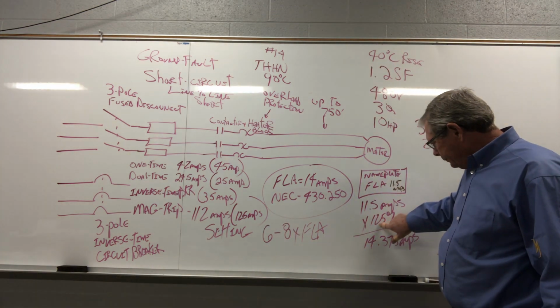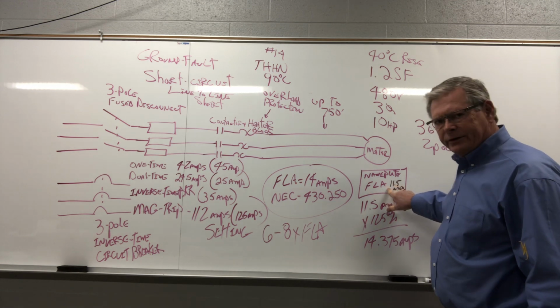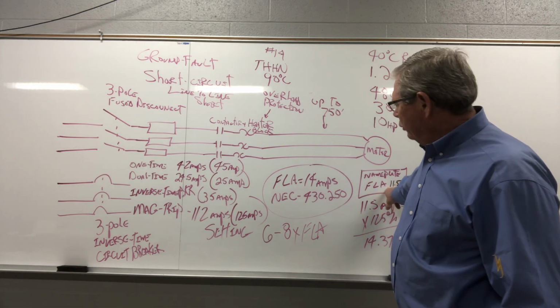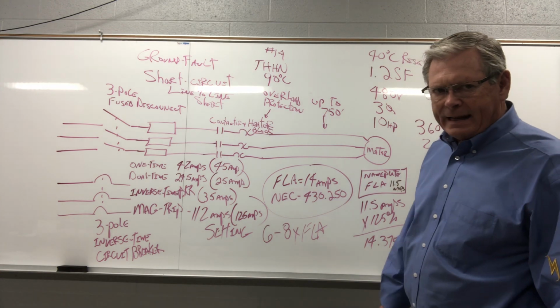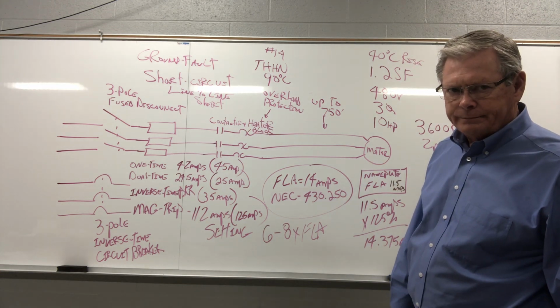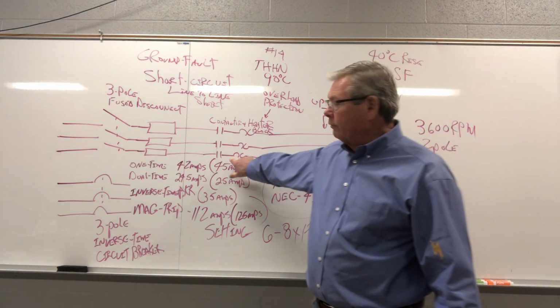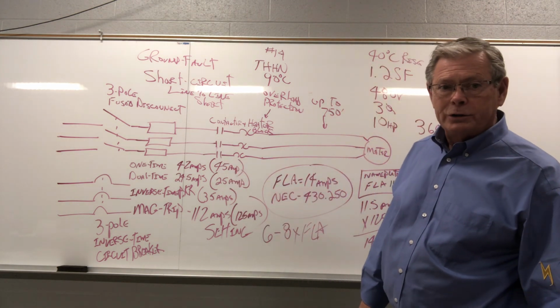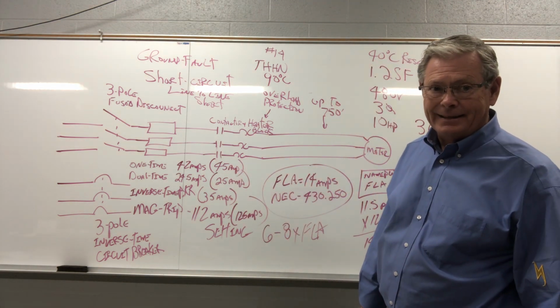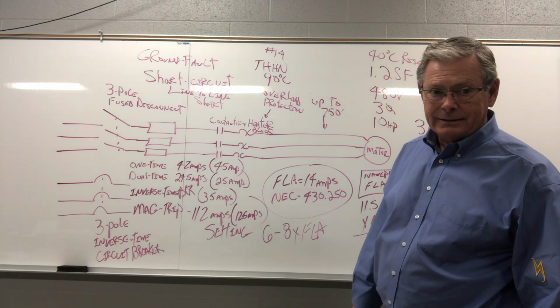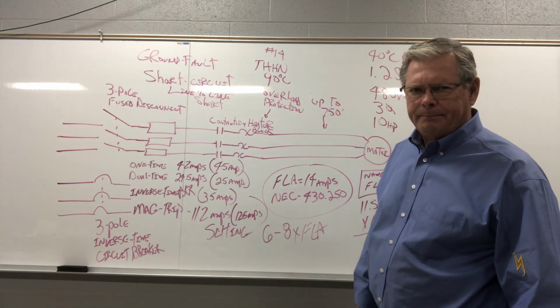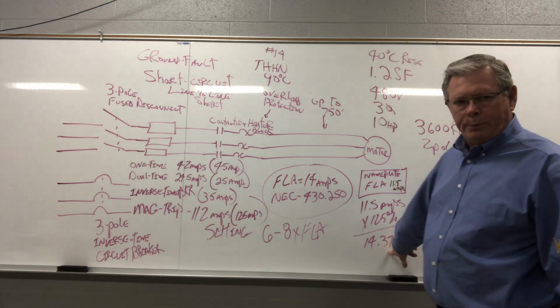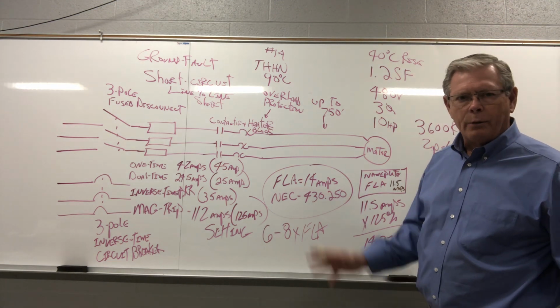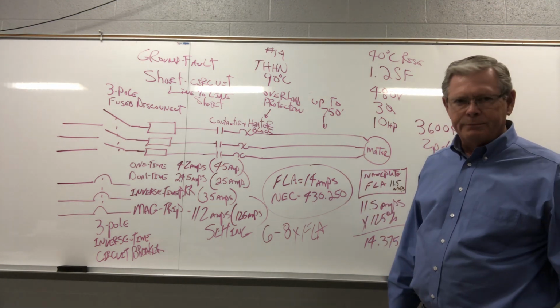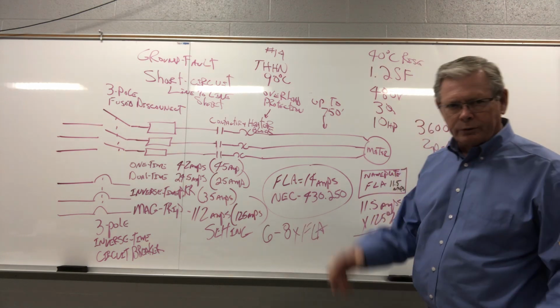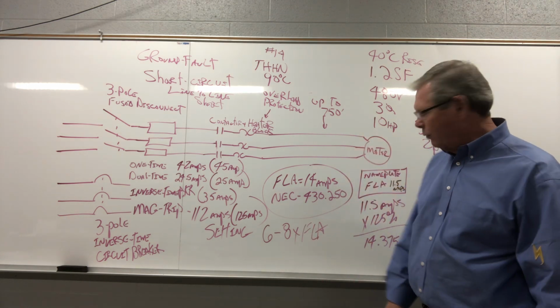So, if you select heaters at 11.5 amps, you're only asking for 80% of the horsepower out of that motor. In other words, this overload is going to trip out at 8 horsepower off the end of that shaft instead of 10. Okay? Give or take, all right? Why is that important? Well, everywhere I've ever worked always wants to run more and more on a given piece of equipment, or wants a pump to run harder, or pump stuff you've never pumped before.